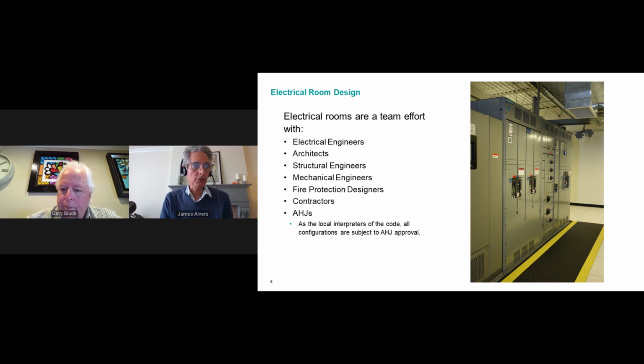And an important thing that sometimes gets missed is space for anticipated expansion. If you have future breakers, it means you may need a future ATS, and you need to consider the pathway for some of the wiring. Obviously, proper illumination and ventilation. So you have to get the whole team together. And most importantly, as a vendor, we see quite a few different designs, and the AHJ is the ultimate interpreter of the code. So you need to make sure they're involved, because something we may see in California may not be acceptable in Florida or somewhere else.